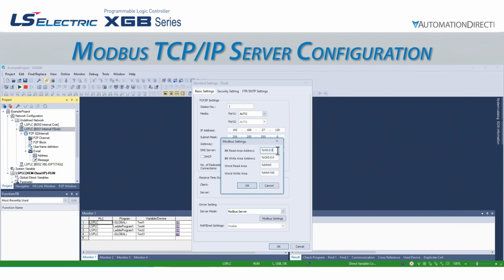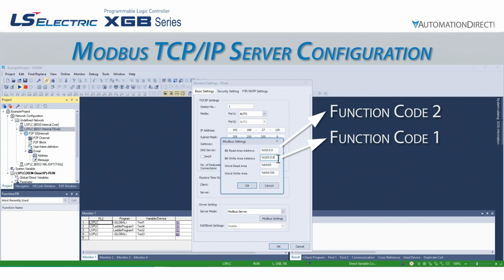The bit read area address will be the internal memory location starting address that will be accessible from a Modbus function code 2 read input status. The bit write area address will be the internal memory location starting address that will be accessible from a Modbus function code 1 read coil status, code 5 for single coil, or code 15 for multiple coils.